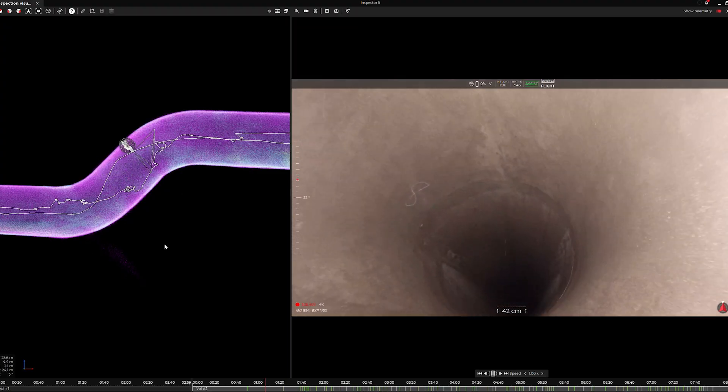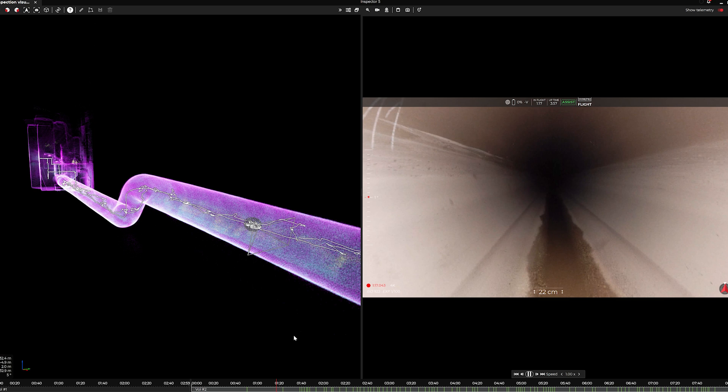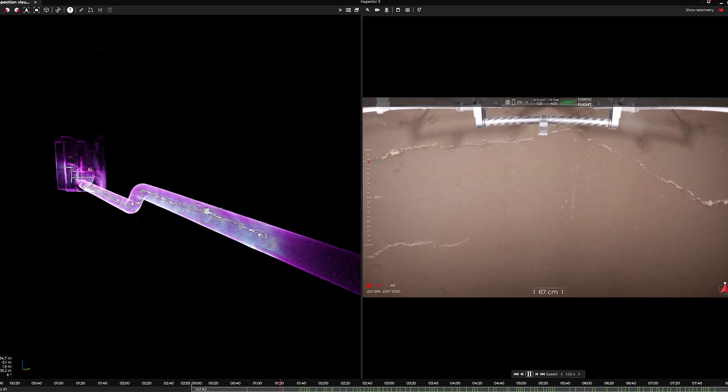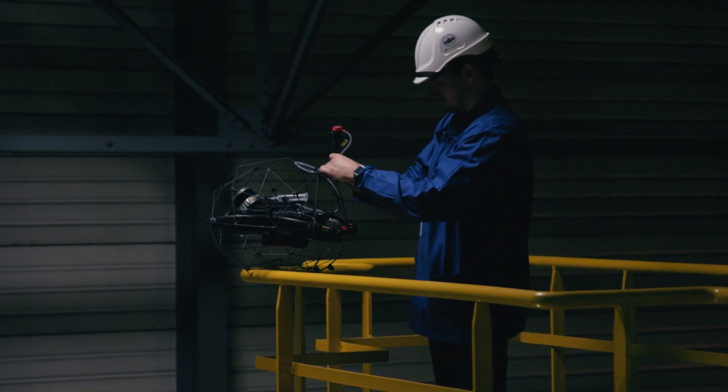Imagine being able to know exactly where each defect is located and going back to it within minutes to know exactly how it is evolving. And for steel penstock operators, the Elios 3 drone is also equipped with a UT probe to perform remote UT inspections. All this data is stored forever — it's reviewable and easy to share.